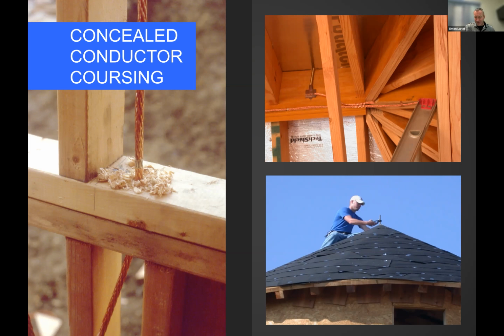But yes, you can run conductor on the interior of a building. It doesn't heat up appreciably. The way to think about that is the tungsten element in your toaster heats up because it's resistant. It heats up and it toasts your toast because it's not that conductive. That's fine. Lightning protection conductor, on the other hand, is electrical grade copper or aluminum, and so it's not going to heat up appreciably because it's super conductive.